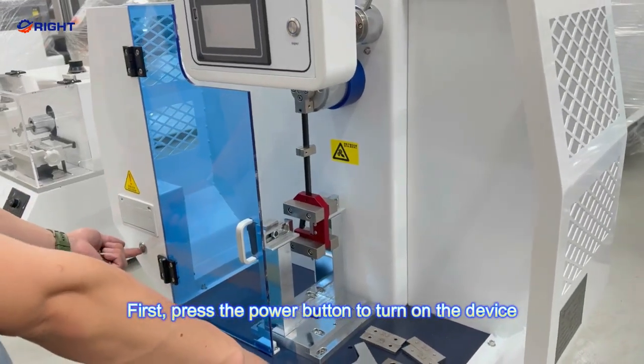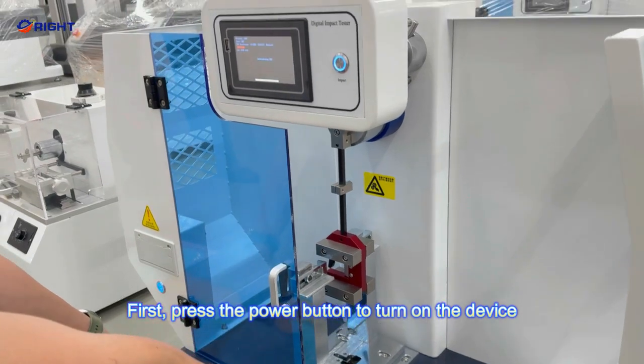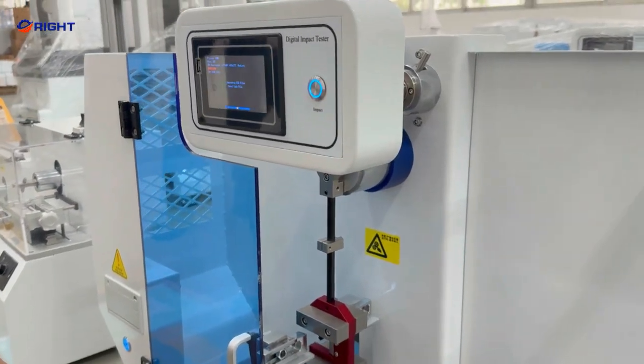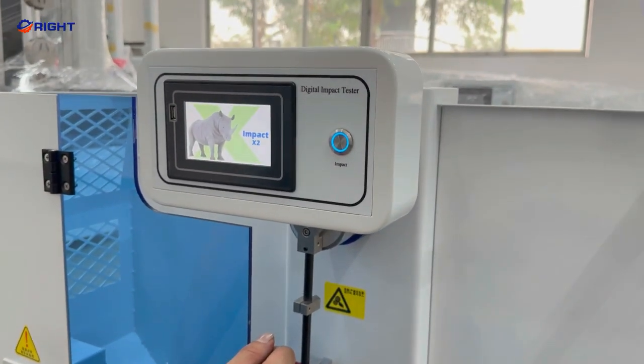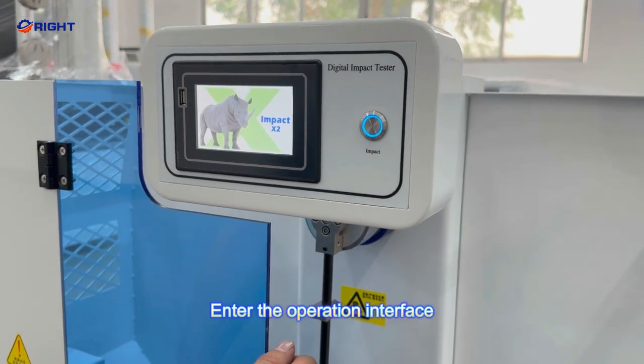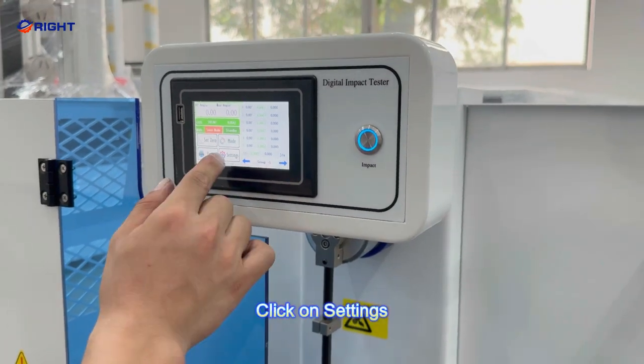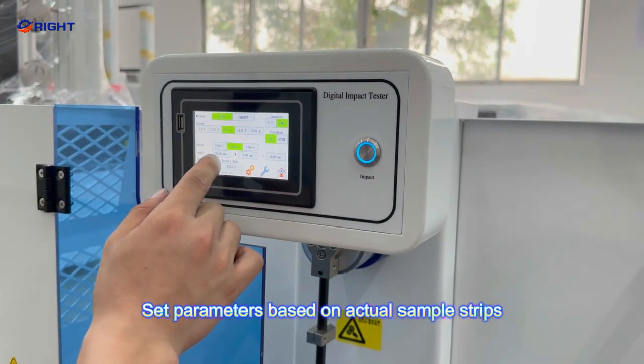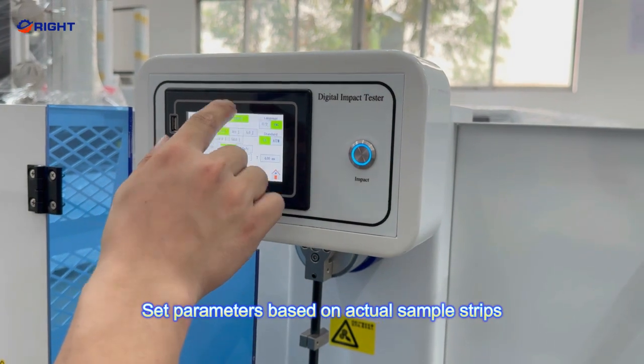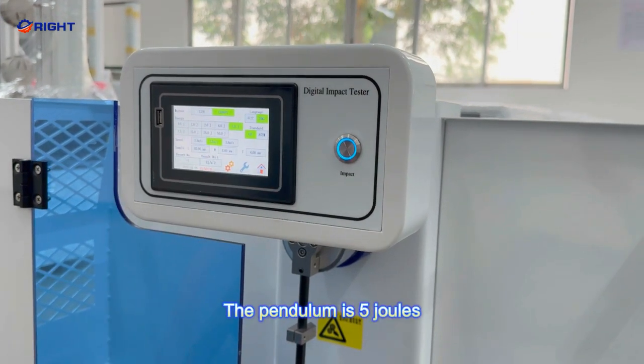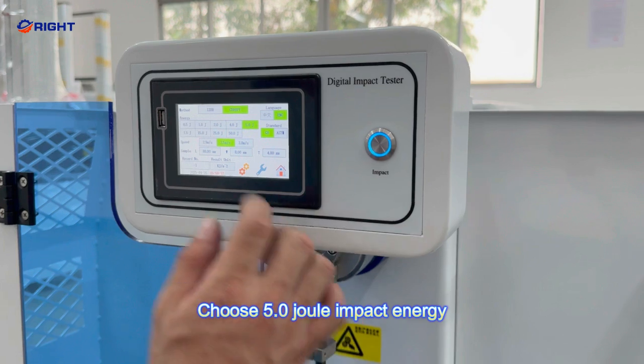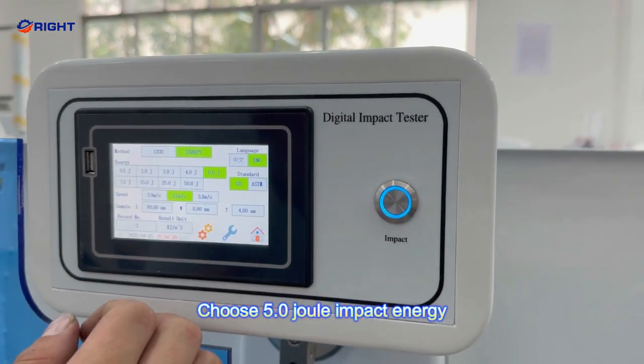First, press the power button to turn on the device. Enter the operation interface. Click on Settings. Set parameters based on actual sample strips. The pendulum is 5 joules. Choose 5.0 joule impact energy.